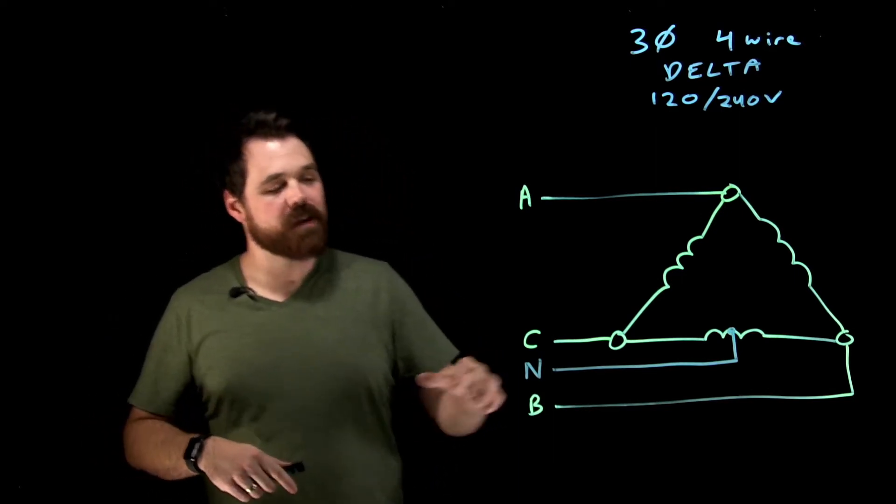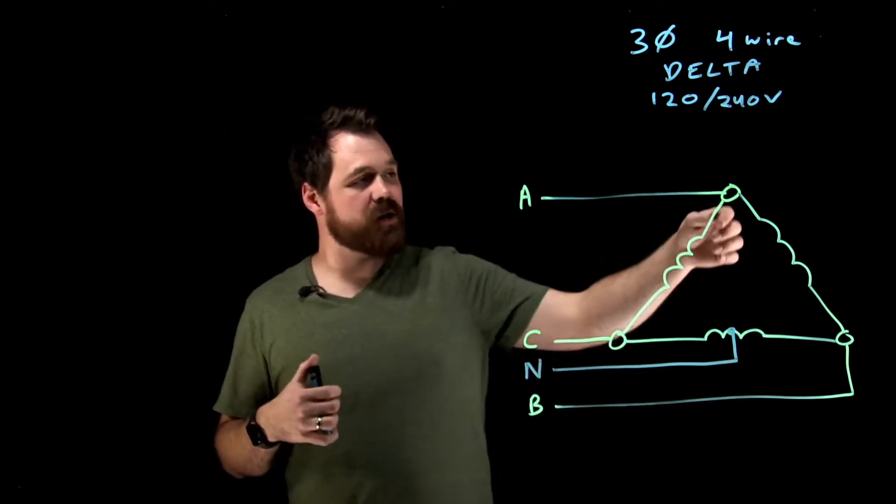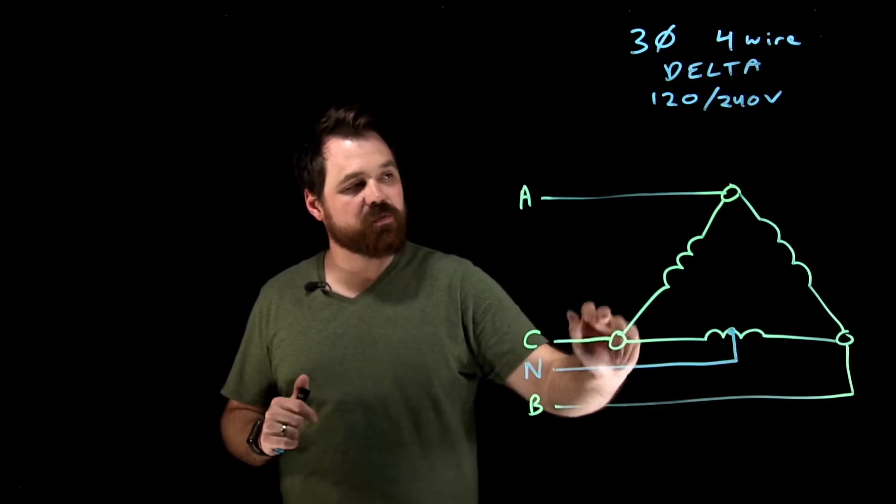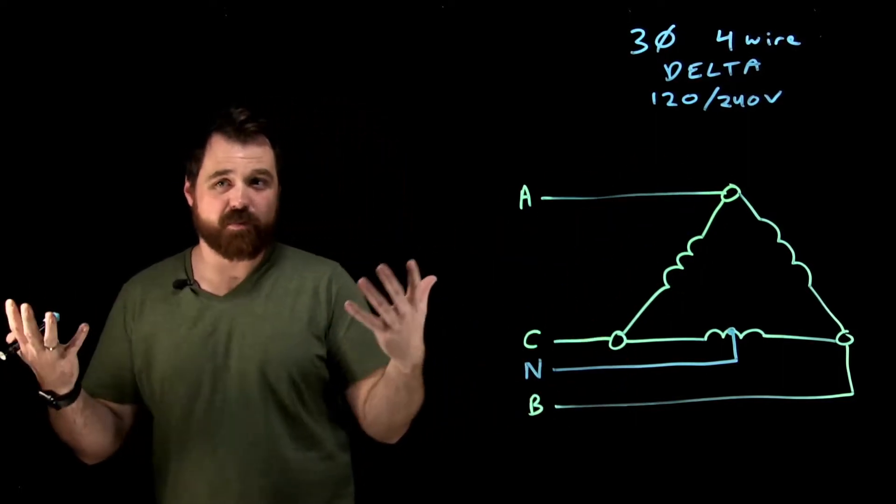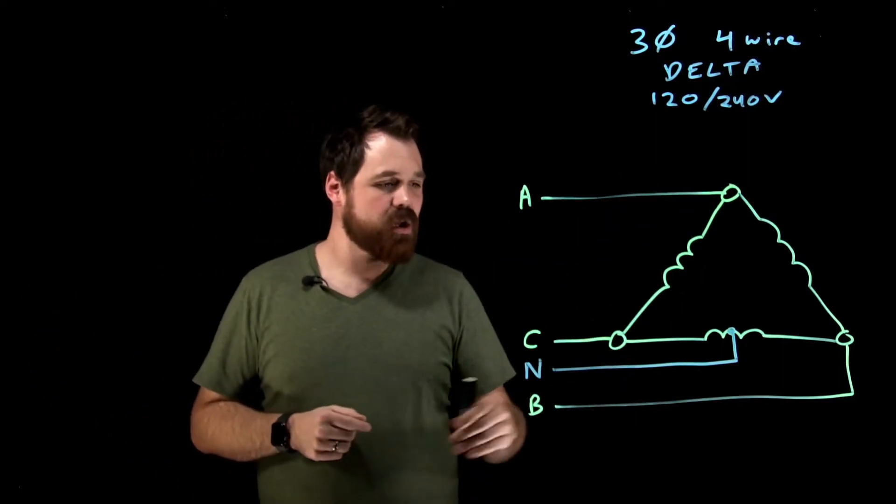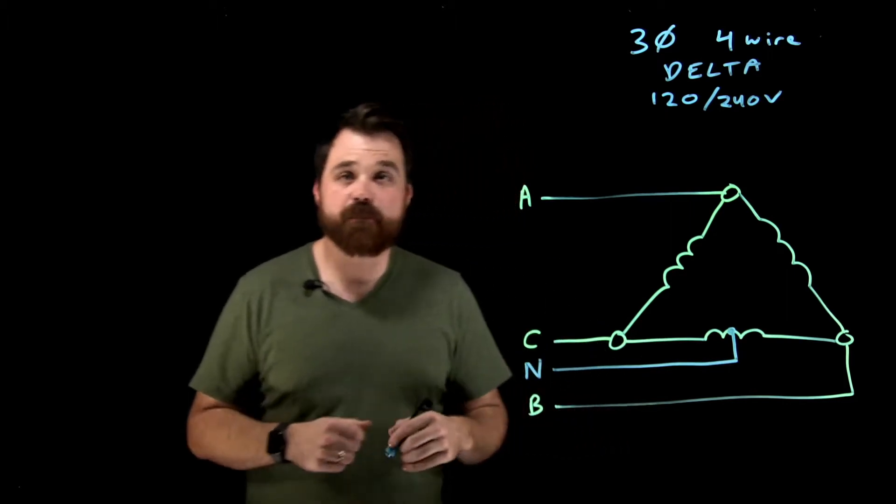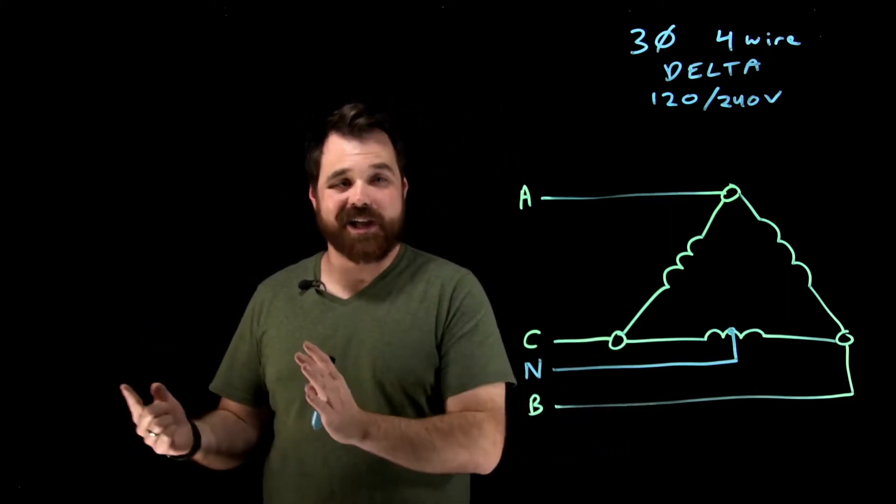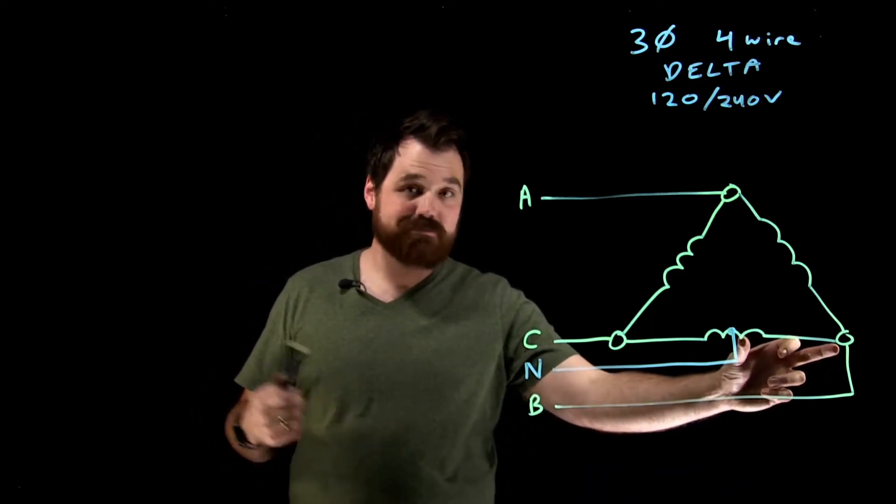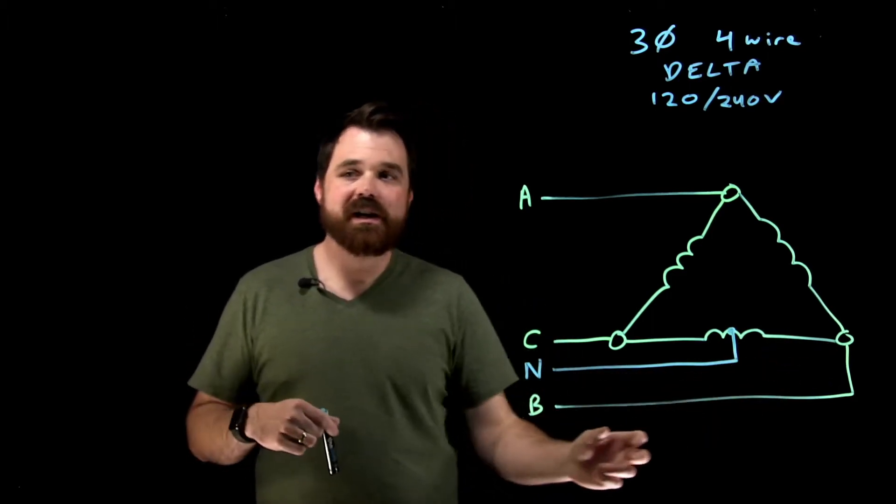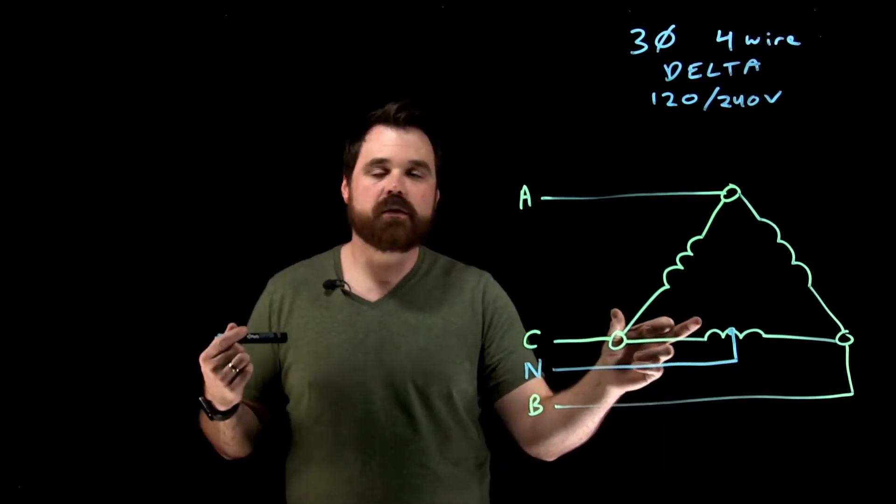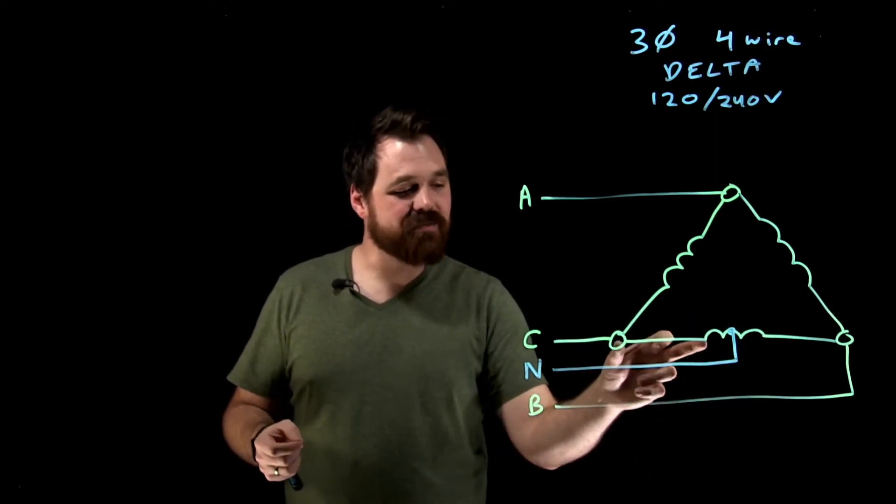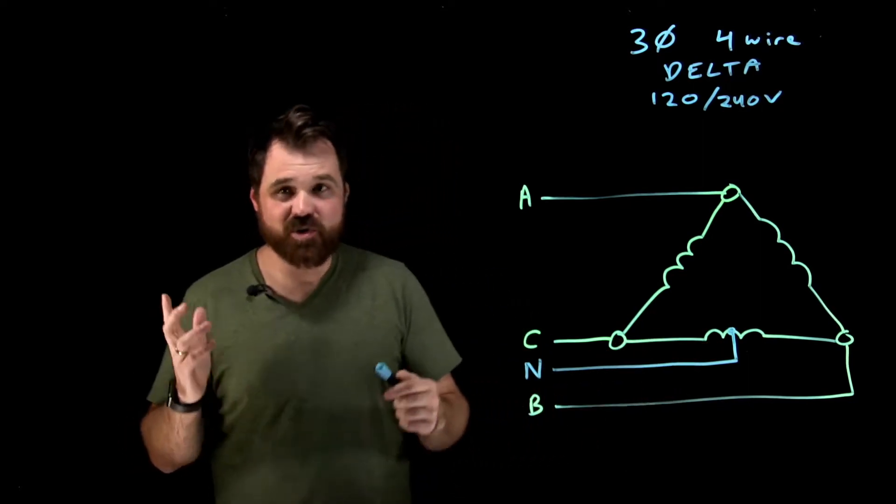Now, what we see there, because our voltage was from A to B 240, from B to C 240, and from C to A 240, our three-phase delta voltages, when we center tap that winding, we're taking a 240-volt winding and we're cutting it in half. Meaning from B to N I get 120 volts, and from C to N I get 120 volts.